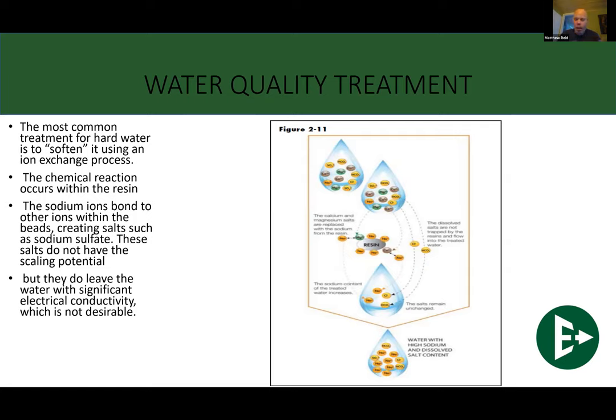Filling it with soft water. I hear a lot of people, they get their horror stories about dielectric unions. In a lot of those cases, once we do a bit of diving in and figuring out what's going on, it's usually filled with softened water from inside the house. And unless it's a top quality dielectric union, it's going to fail. And not only that, that is really what they're designed to do anyway. They're designed to take that failure inside of themselves, as opposed to having that failure be somewhere else, more catastrophic inside the system. At least with the union, you can change those out. Anyway, softened water does decrease scale, but it creates another problem.